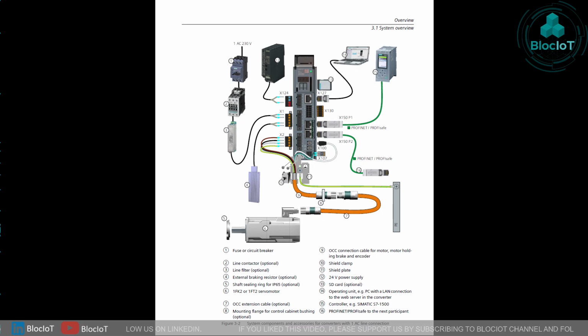And that's normally the first thing you need to look at when you're getting a new servo drive or any kind of drive. So in the center, we have the S210 new drive, and on the bottom, we have the servo motor itself. And as I explained, you have the prefabricated cable that connects the motor to the drive. It's just a very easy way to connect the cable to the motor. You just push it in and rotate it. And on the drive side, you have the connector for the encoder. You have the connector for the motor power. That's the output from the drive, but the encoder is an input to the drive from the motor.